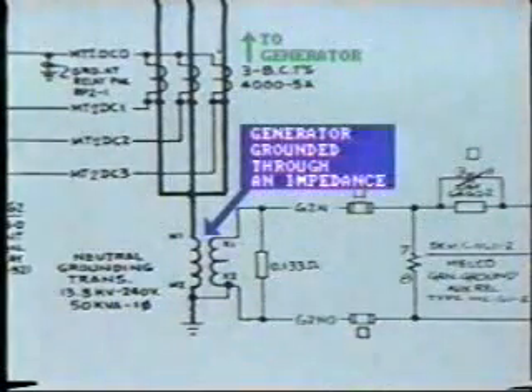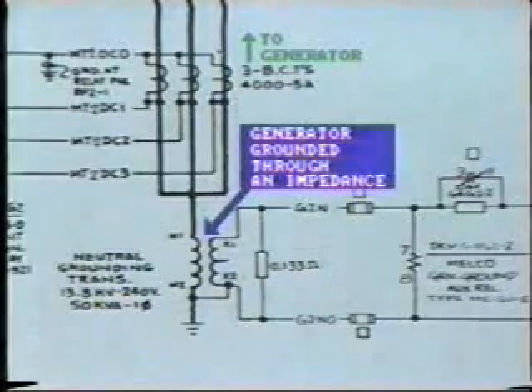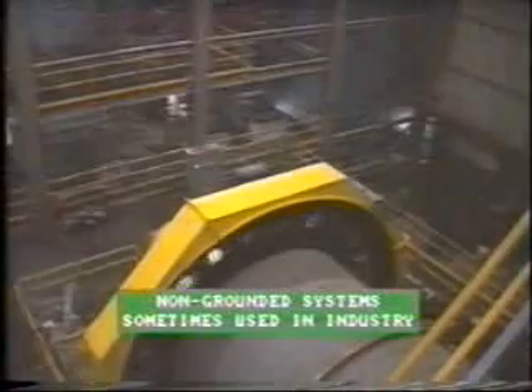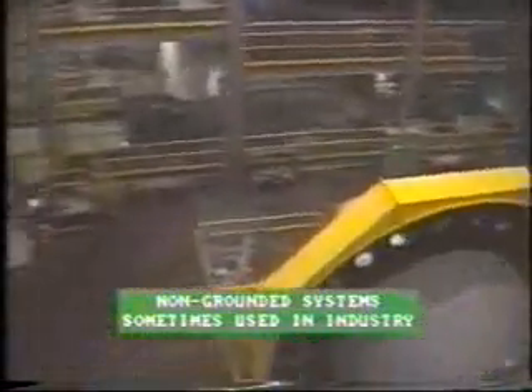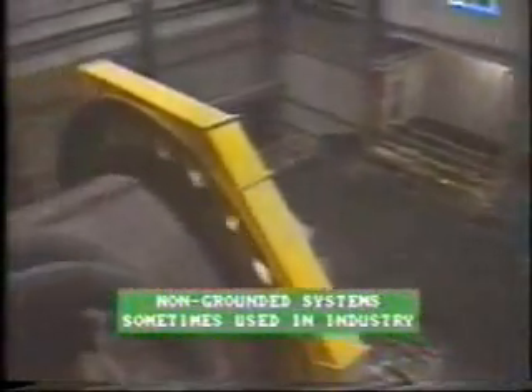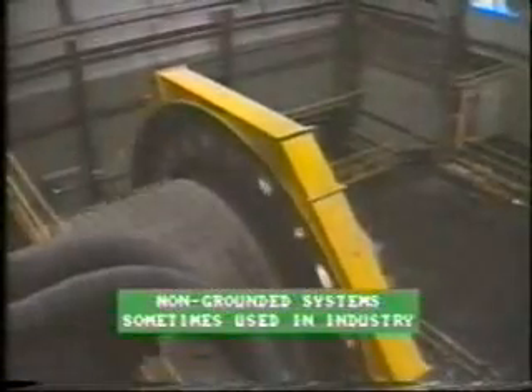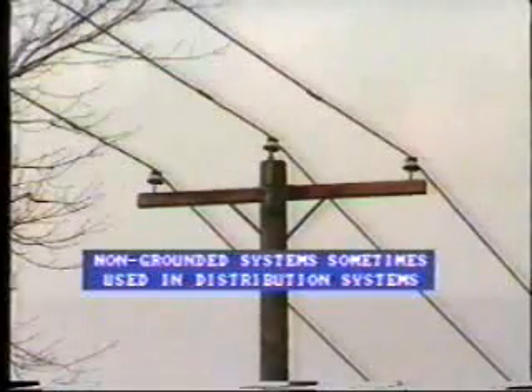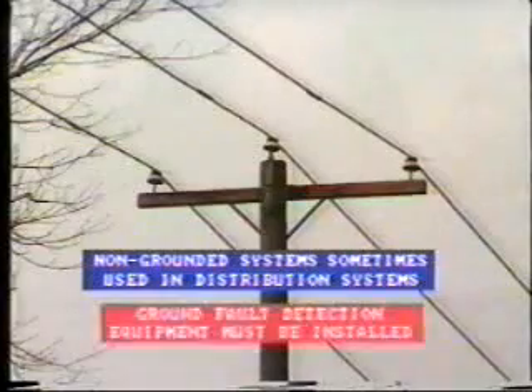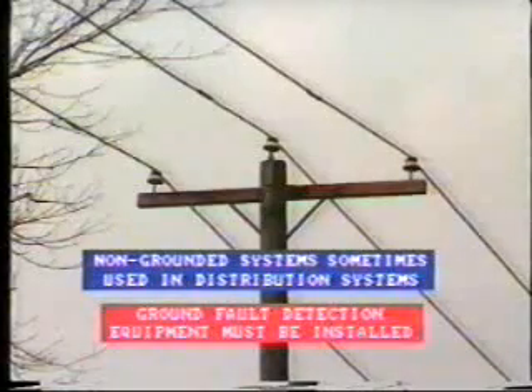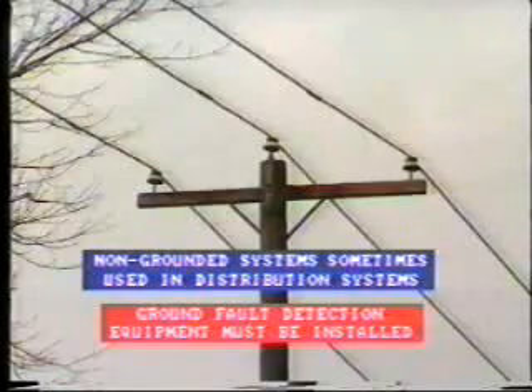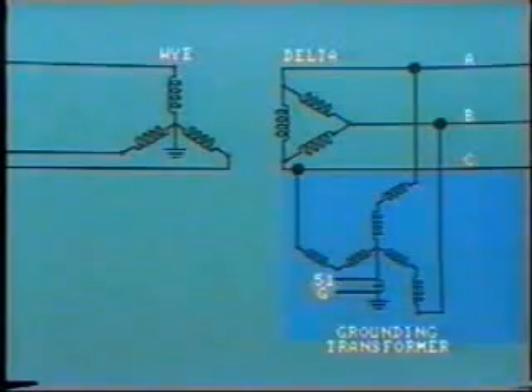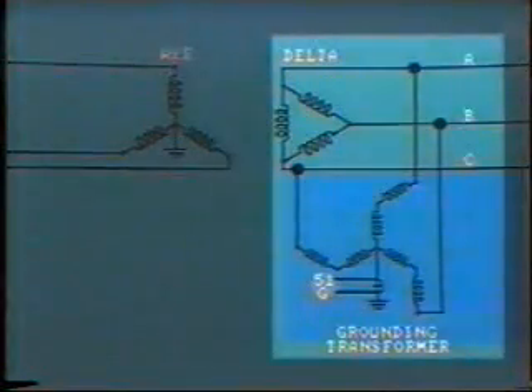Generators may be grounded through an impedance so as to limit the magnitude of fault current. Non-grounded systems are sometimes used in industry where a continuous power supply is required. Distribution systems are sometimes not grounded, and in this case, ground fault detection equipment must be installed. Delta systems can be grounded with grounding transformers.